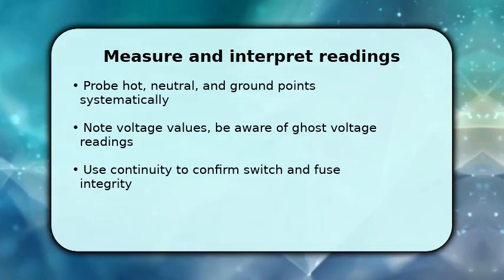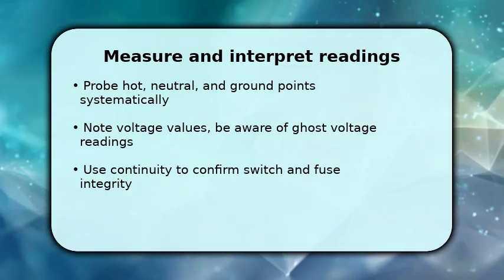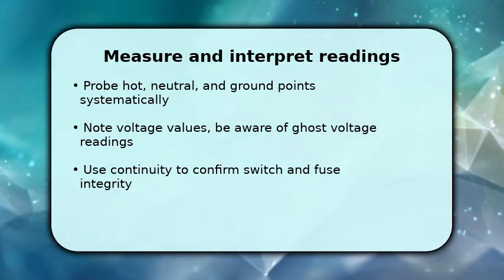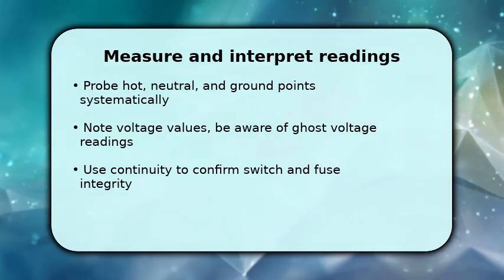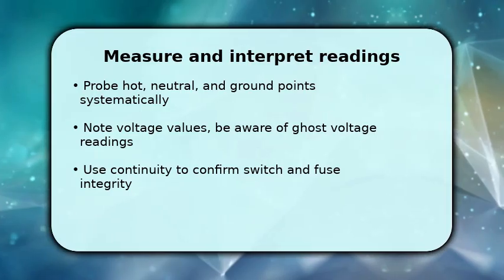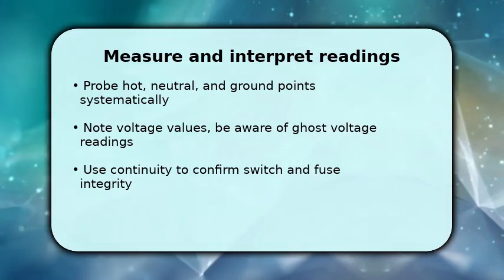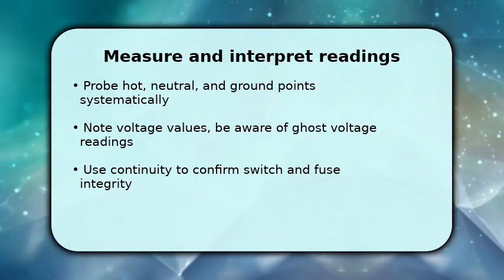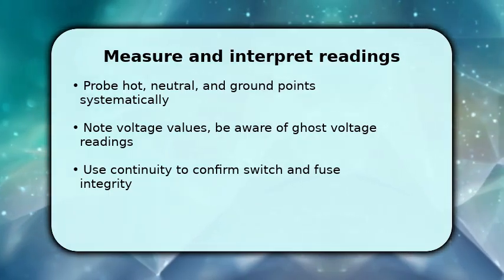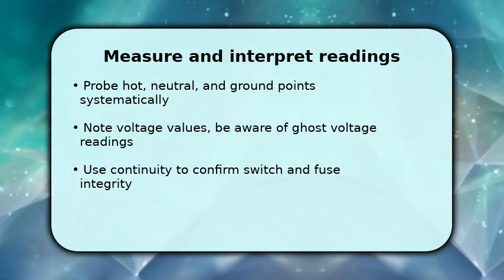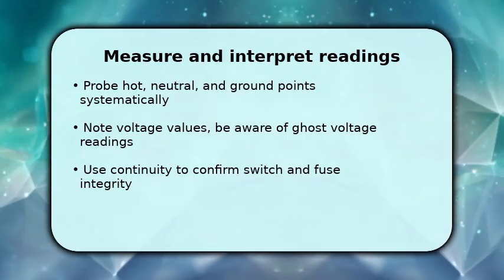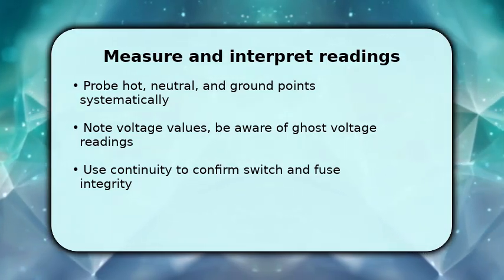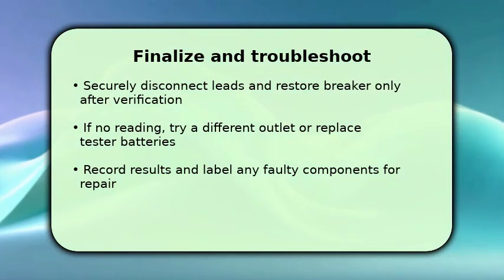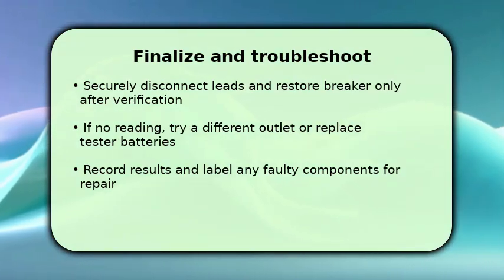If you see low or fluctuating voltages, consider ghost voltage, load the circuit briefly, or use a low impedance mode to confirm. Use continuity mode across switches, fuses, and connections to verify closures. A steady beep means good continuity. Make sure to move slowly and recheck suspect points for accurate interpretation.